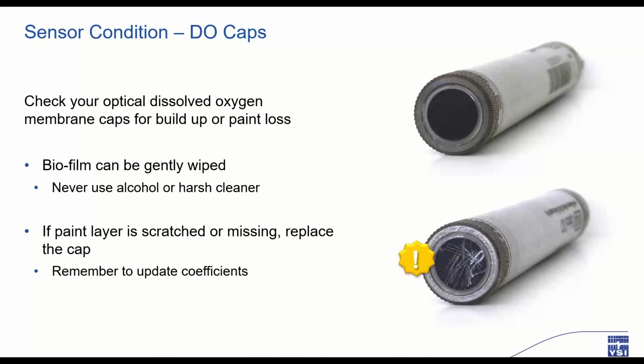This paint coating is designed to help keep ambient light out of the sensor. This paint is not involved in the process of determining the DO value. That magic actually happens behind this curtain. However, if a quarter to a third of the paint is missing, then you will likely see unstable readings and have difficulty calibrating, and the membrane should be replaced. This process is super easy with the DSS and EXO. The new membrane just screws on, and it comes with a new O-ring, Krytox, and its own individual set of coefficients that you'll enter into the software prior to calibrating with the new membrane installed.